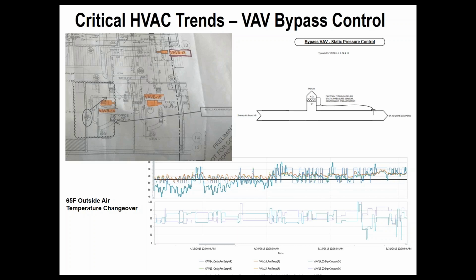And there was control related to, is the heat pump in heating? Is the heat pump in cooling? And how do we manage the needs of both zones at the same time? So this bypass VAV control scheme came into play. What I wanted to see here was, first and foremost, are we maintaining space temperature set points in the zones? And then, system related, are the dampers actually working the way that we think they're working? Generally, I did see the dampers working opposite of each other, and I did see that the zones were controlling pretty well within set point. So although slightly more complicated than what we would have liked, my take from this was that we were actually satisfying the needs of those spaces.